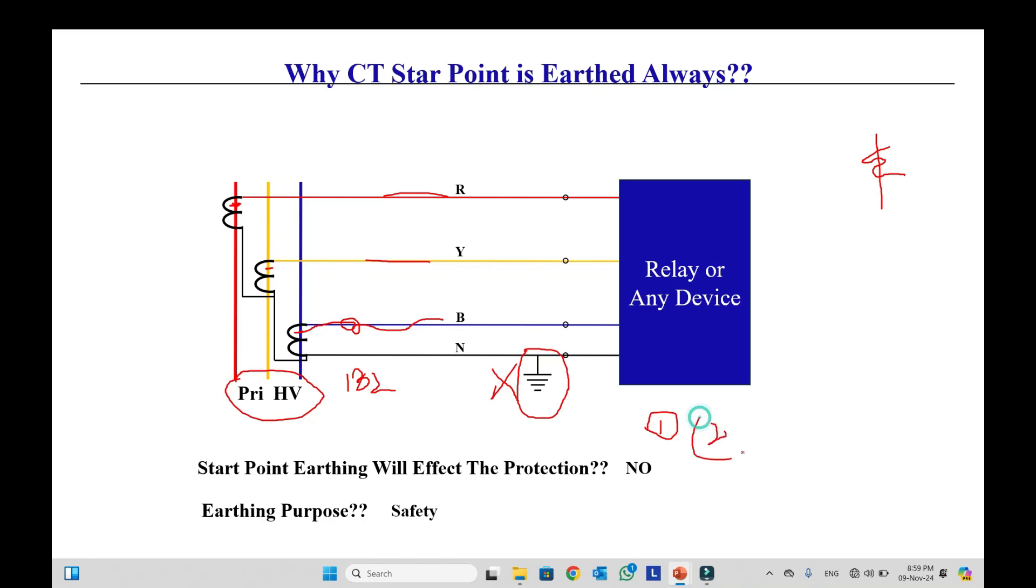In the running system, in the healthy system, we have this high voltage in the primary side and very low voltage in the secondary side. So there is a capacitance due to insulation. There is a capacitance between primary and secondary. Due to this capacitance, our secondary may get some voltage induced. Our secondary side may get some voltage from the primary side.